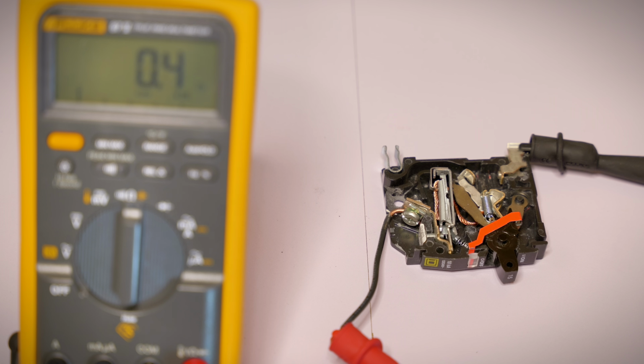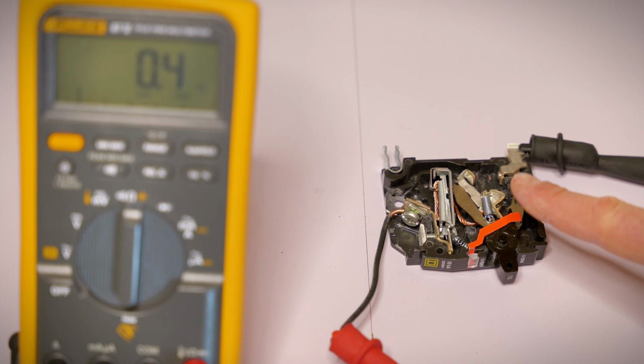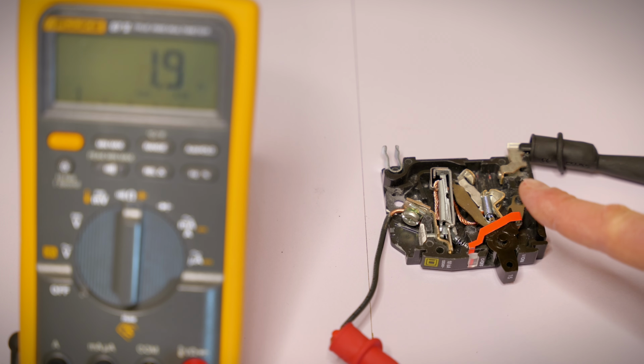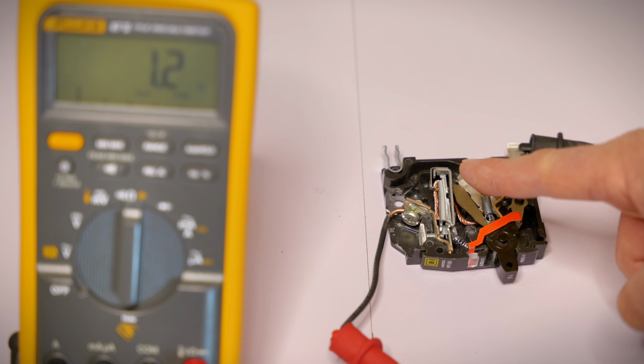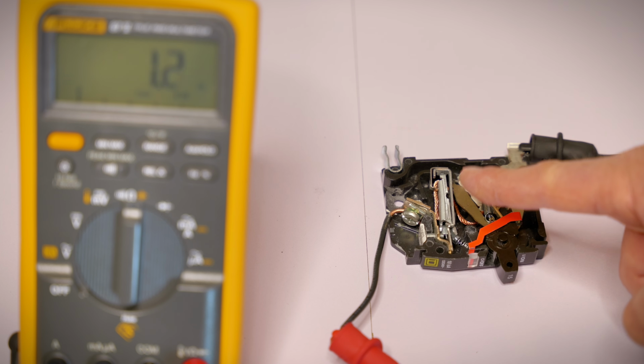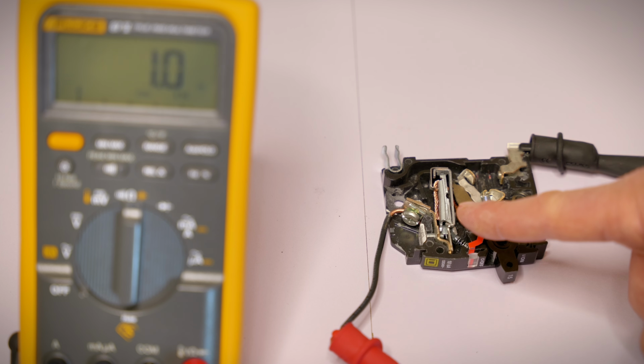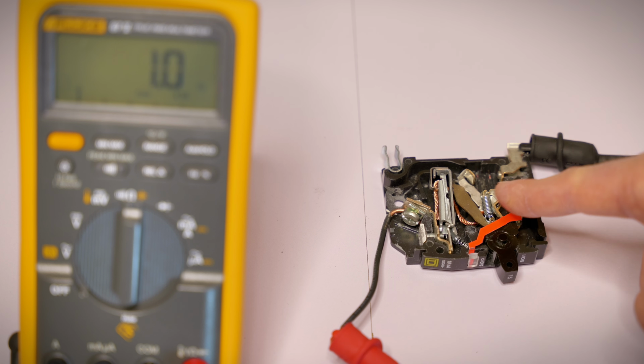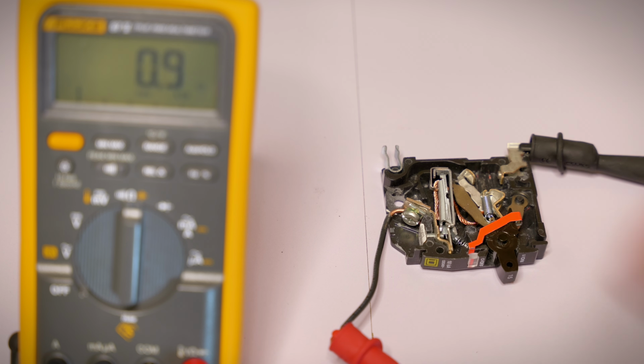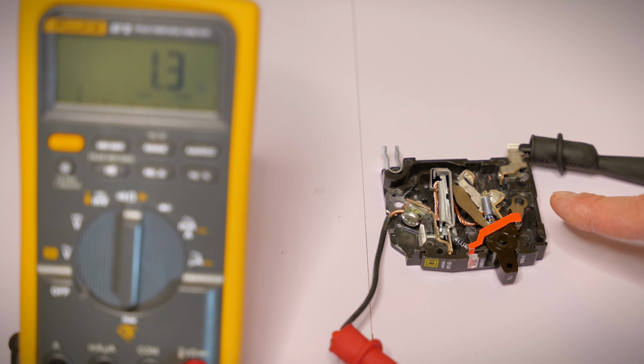Now this is probably the most dangerous situation, because if this happens, which is fairly rare, but if it were to happen, your circuit breaker is no longer working in the circuit, and if something did trip that circuit breaker, it means something is overloaded, overheating, and it could cause a fire in your house. So if you have this condition, you need to immediately remove all your main power to your circuit breaker panel and get the circuit breaker out of there.